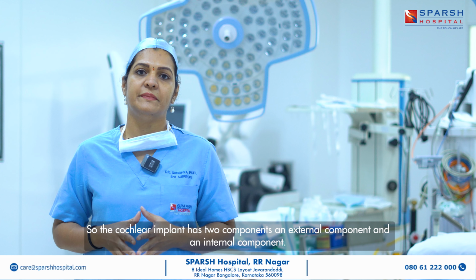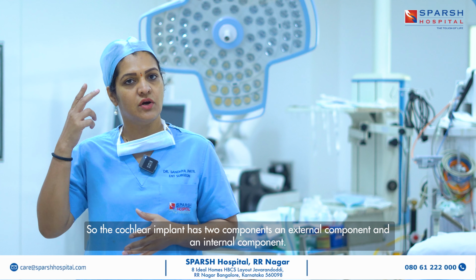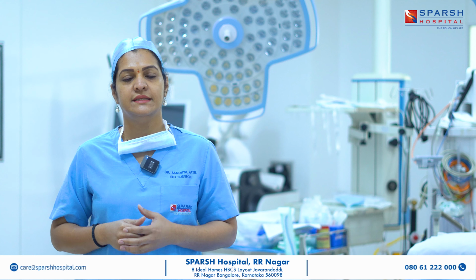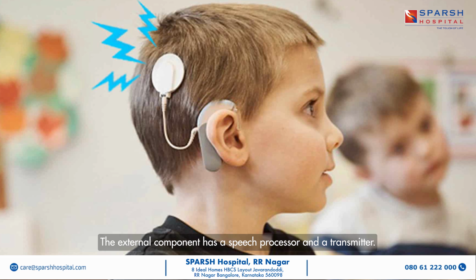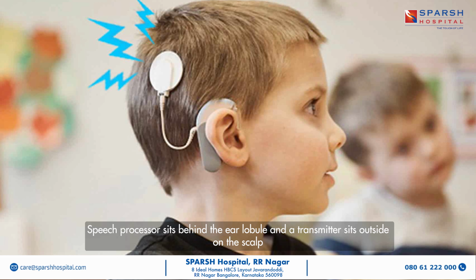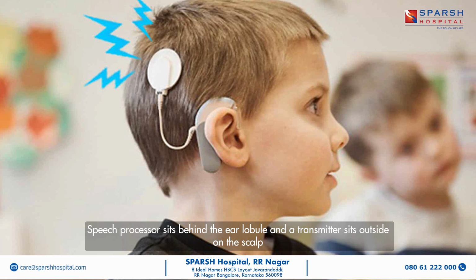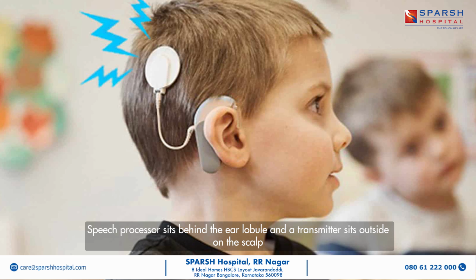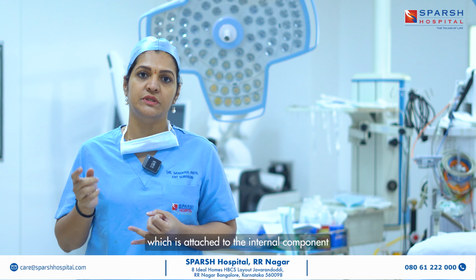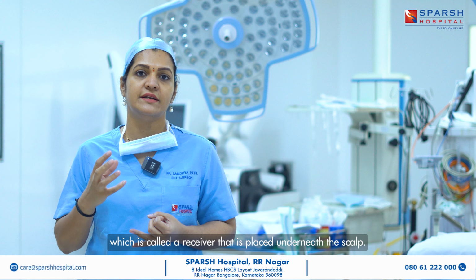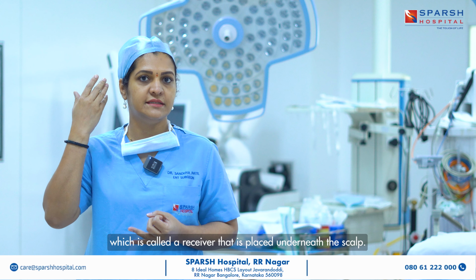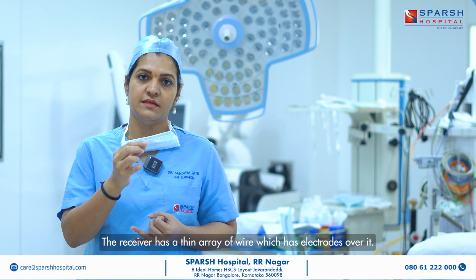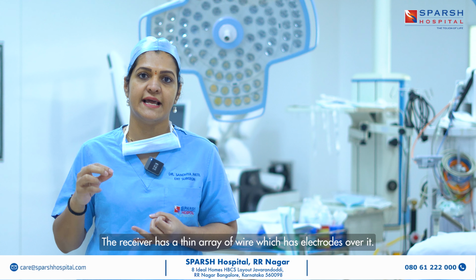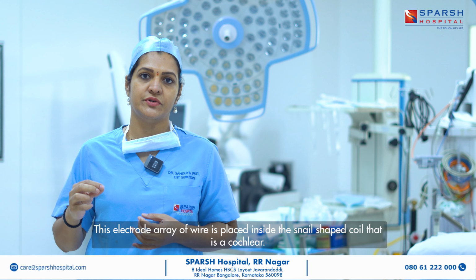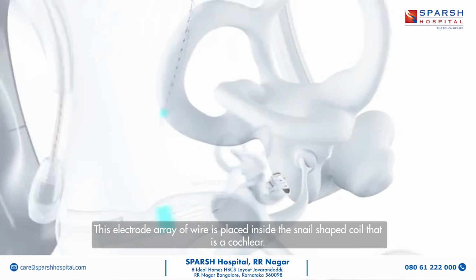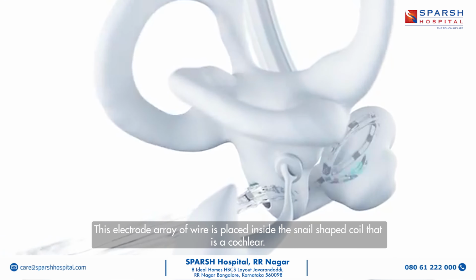So the cochlear implant has two components, an external component and an internal component. The external component has a speech processor and a transmitter. The speech processor sits behind the ear lobule and a transmitter sits outside on the scalp, which is attached to the internal component, which is called a receiver, that is placed underneath the scalp. The receiver has a thin array of wire which has electrodes over it. This electrode array of wire is placed inside the snail-shaped coil, that is the cochlea.